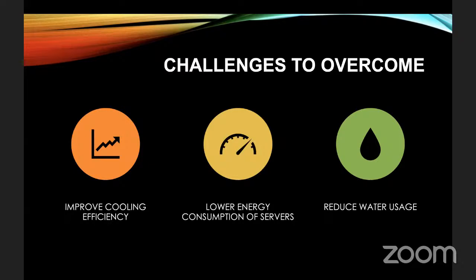And the one in the middle is the one to target. If you can lower the energy consumption of the servers, then you will automatically be able to improve the cooling efficiencies and reduce the water usage. So how do we go about doing that? Well, there are different strategies that we can employ. Strategies for improving cooling efficiency would include changing to something such as submerged cooling technology.